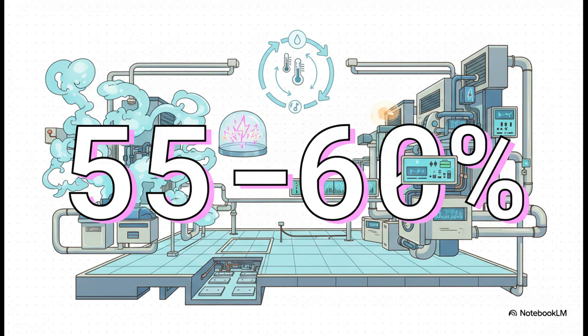But it's the humidity metric that's honestly the most shocking. It has to be maintained exactly between 55 and 60%. If it drops too low, static electricity can build up. And when you're in a room where highly flammable anesthetic agents are being used, a single electrostatic spark can literally cause a lethal explosion. No joke. The climate control here is a literal life or death metric.